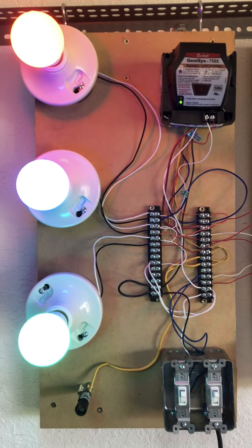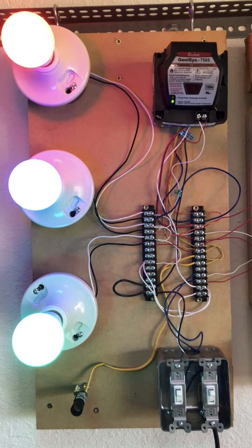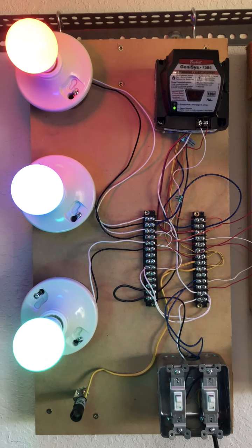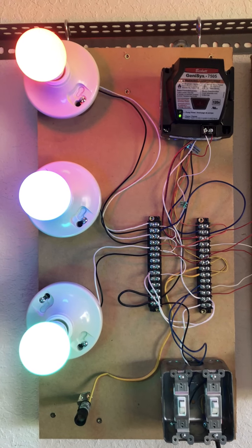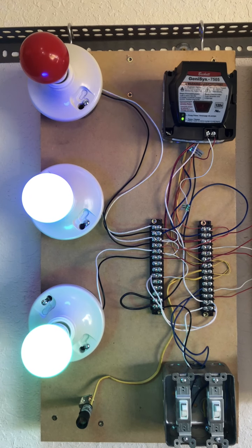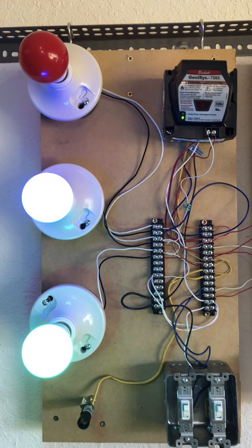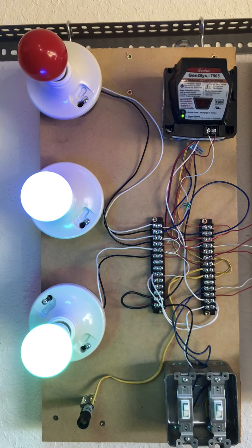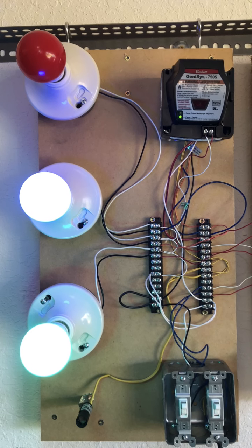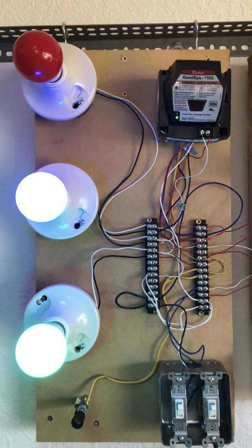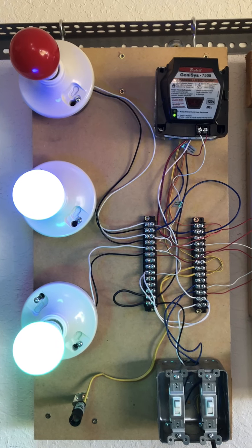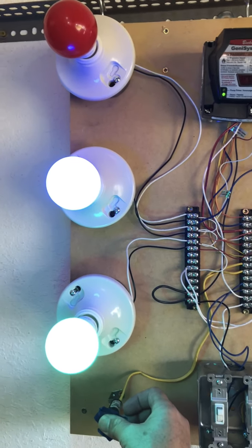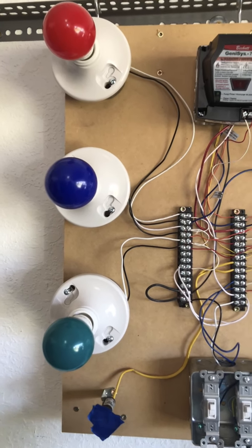Now there's a safety in here that once the ignition sequence is complete, which we'll have momentarily when the top light goes out, my igniter isn't running anymore. As long as the igniter's off and I have flame, we're fine. Now what happens if the flame goes out? We don't want to continue dumping unburned oil in here. So now the flame goes out. See how fast that shuts down?